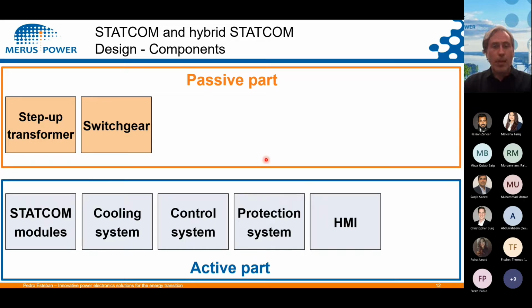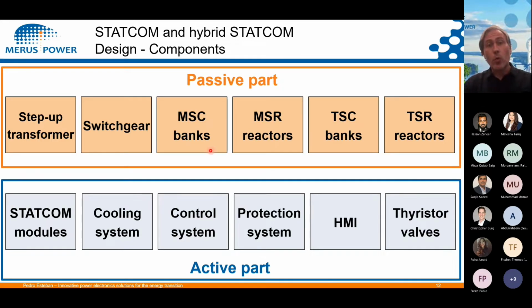If we are thinking about a hybrid STATCOM, then we will have to add to these components whatever we need for that certain application: capacitor banks or reactor banks that are switched mechanically or with thyristors. And if we are switching with thyristors, we will also have to control the thyristor valves with this control system.